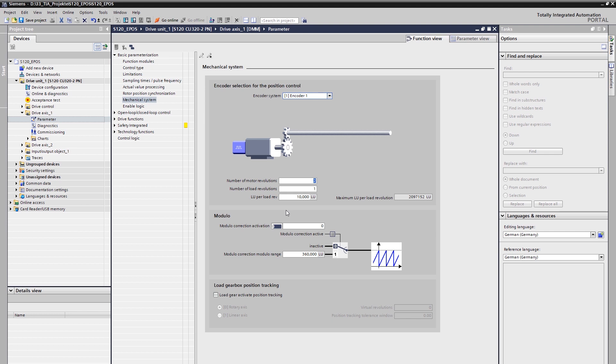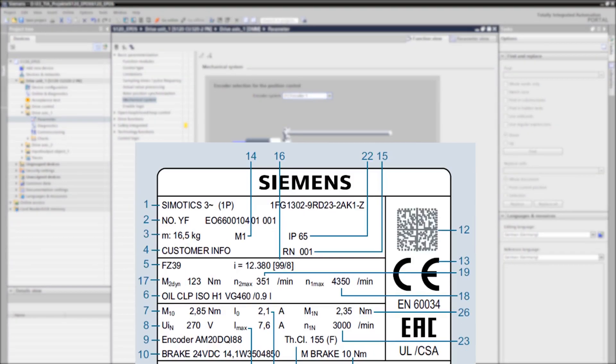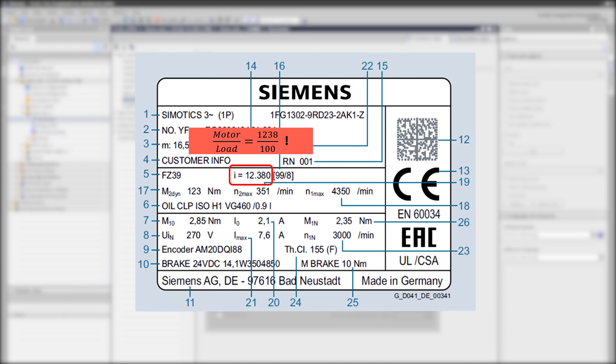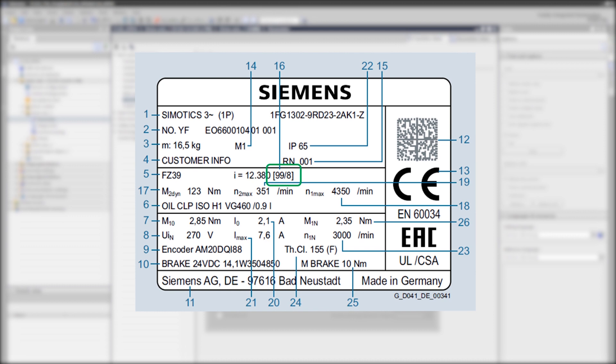Therefore, I would like to give you here an important advice for the input of the gearbox ratio. Gear ratios are often indicated as rounded floating point numbers on the gearbox or motor nameplate. For example, you will find specifications such as 12.38. If you use such a rounded value for the input, thus 1238/100, this leads to a small but measurable position error with each revolution, which would continue to add up with continuously same direction of rotation. To avoid this, the real exact ratio must be entered. If there is no exact specification, the number of gear teeth on the input and output sides can be entered here as the numerator and denominator. This corresponds to the actual transmission ratio of the gear unit and there will be no position deviation due to rounding errors, even after any number of revolutions.